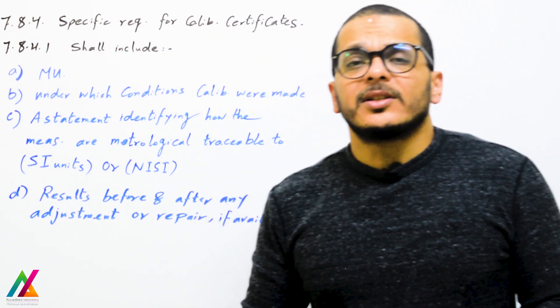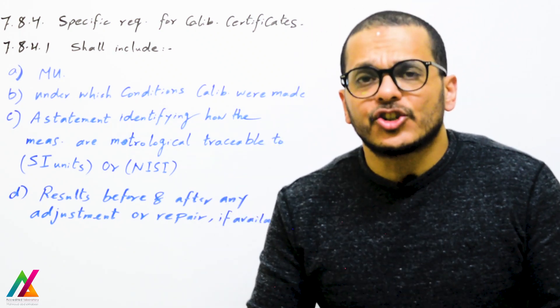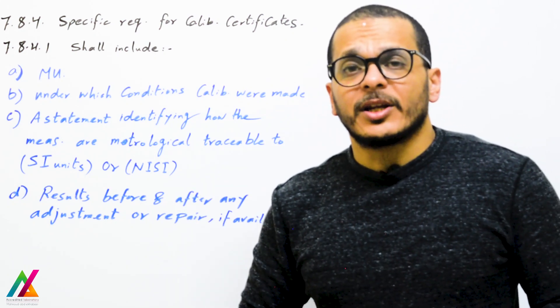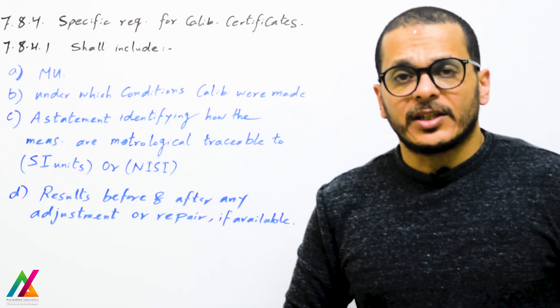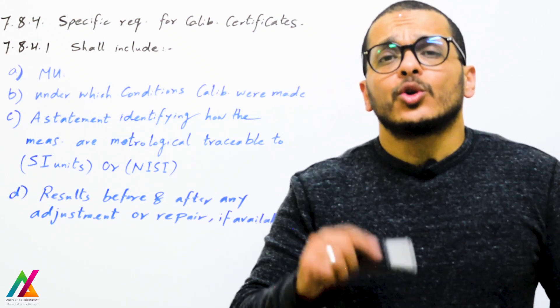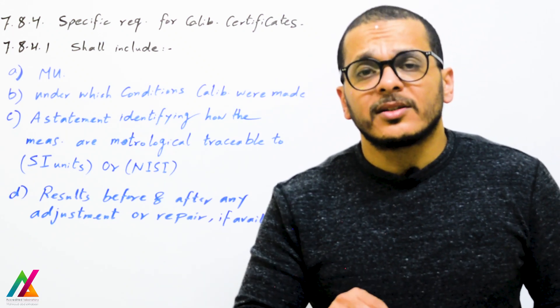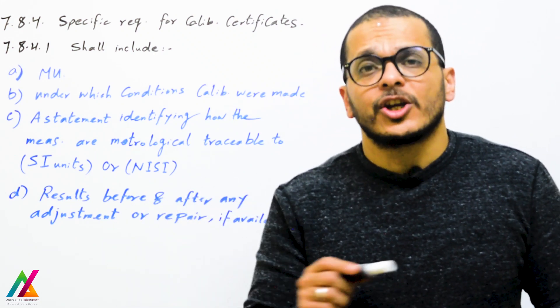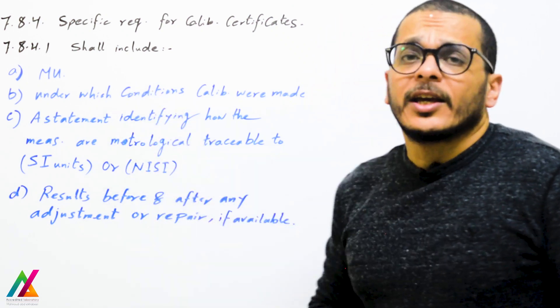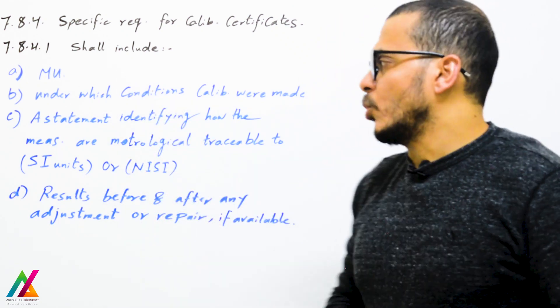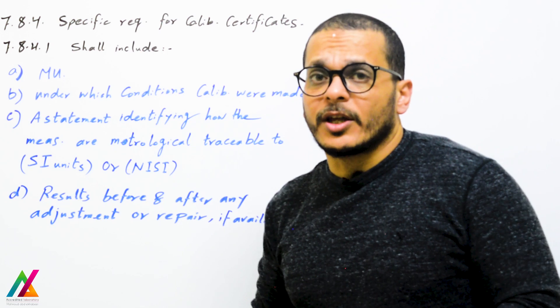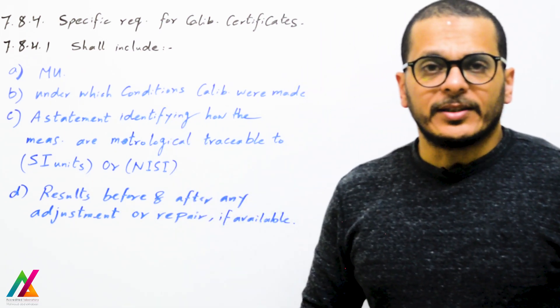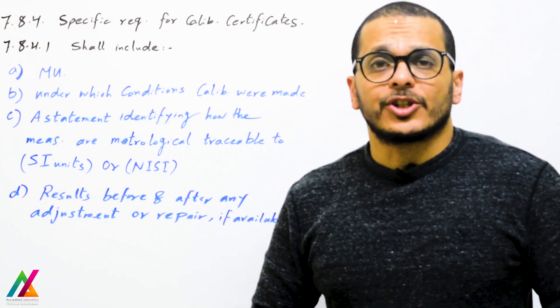The specific requirements for calibration certificates shall include the following. First, measurement uncertainty — this is very important and shall be included in each calibration certificate. Standards or any equipment being calibrated shall have measurement uncertainty in the certificate, because you will use this to quantify the total measurement uncertainty for each analyte, used in Type B evaluation as explained before in measurement uncertainty calculation.